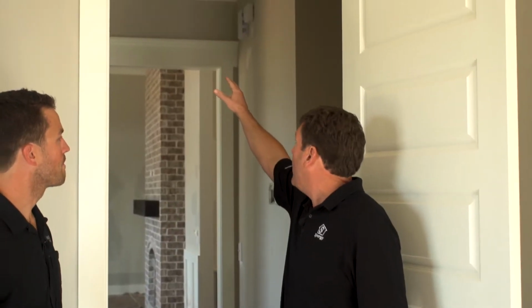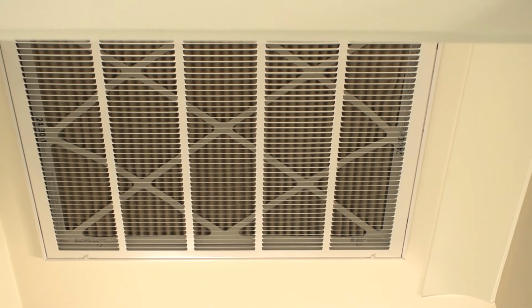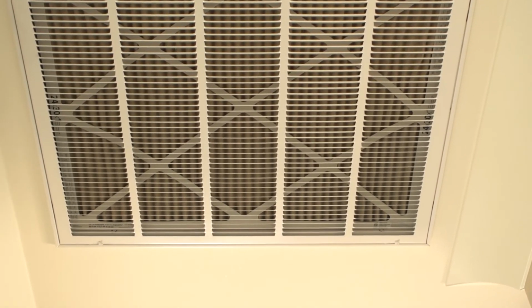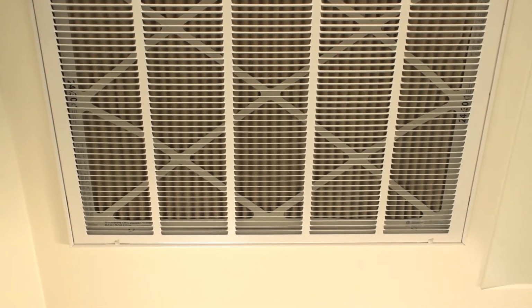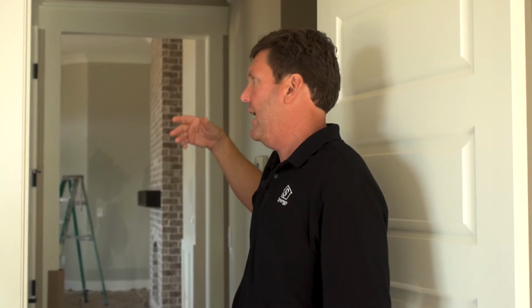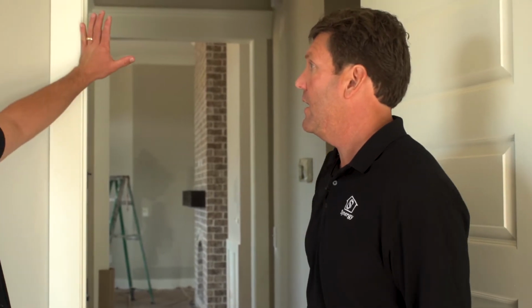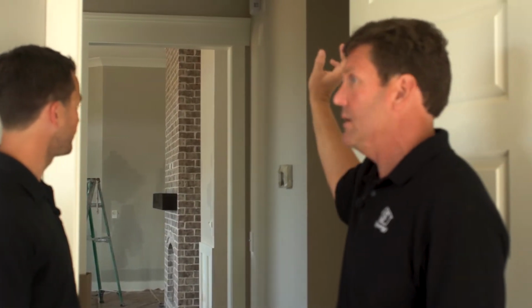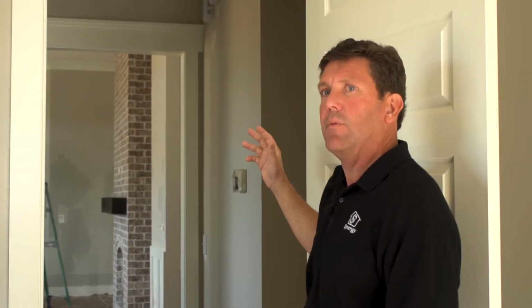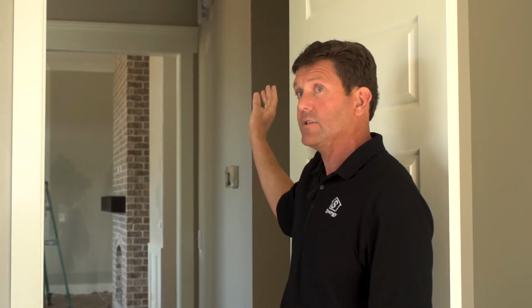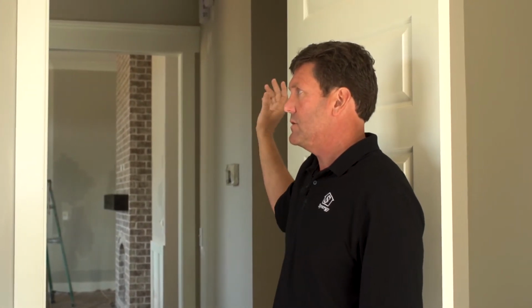If you notice out here in the hall, that's your return duct, which brings all the air back to your unit to be cooled, dehumidified, or heated. That's for the whole house, one big unit. One of the things that happens in a lot of houses is the returns are undersized, so we always want to make sure we have plenty of return.